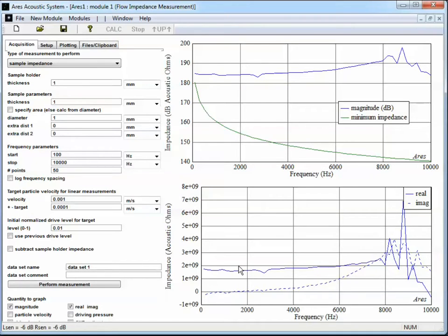Scotch tape over a 1 millimeter diameter hole has a bit too high of an impedance even for the 103A to measure. So that little bit of leak brought the impedance down a little bit and put it within range for the device. But that's how you would measure a sample. Typically, actual microphone covers and whatnot are much thinner than scotch tape, so its impedance is going to come in within the range of the device.